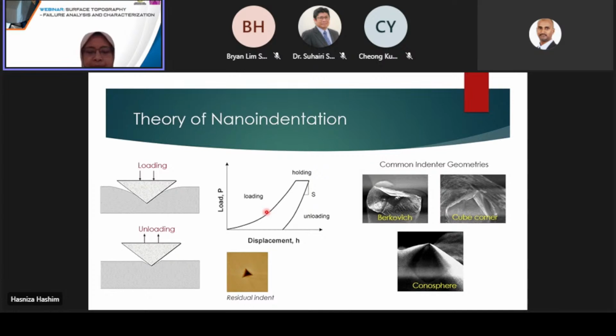Now I would like to explain a little bit about the theory of nano indentation. With nano indentation, a probe of a known shape or geometry and material properties, like this diamond probe, is pushed into a material while continuously monitoring force and displacement. During indentation, the vertical displacement of the probe is measured during controlled loading and unloading phases. Typically, there is some period of holding the tip in place at max load and max depth for some time, which we also call the dwell period.